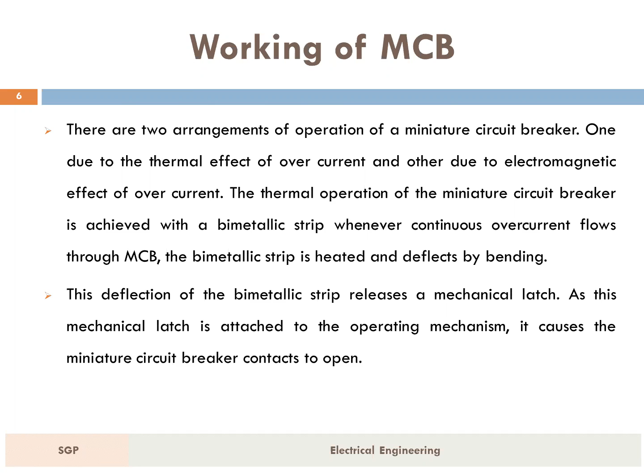But during a short circuit condition, the sudden rise of current causes electromagnetic displacement of the plunger associated with the tripping coil or solenoid of the MCB. There is an example explaining the MCB working principle, which is already shown in the figure. And MCBs are generally used for residential, commercial, and industrial purposes.